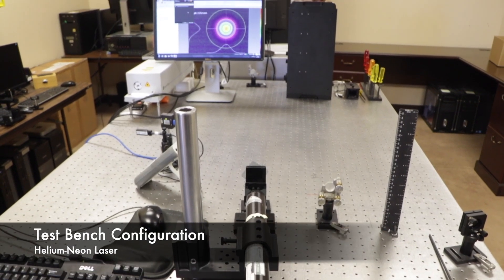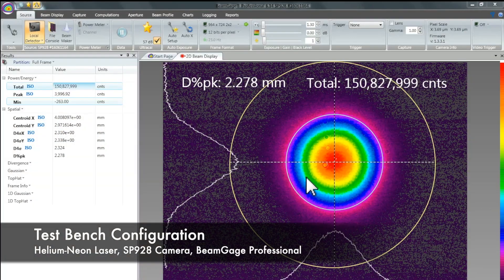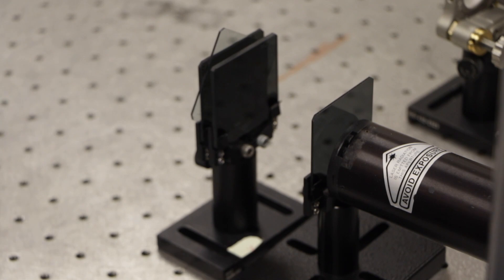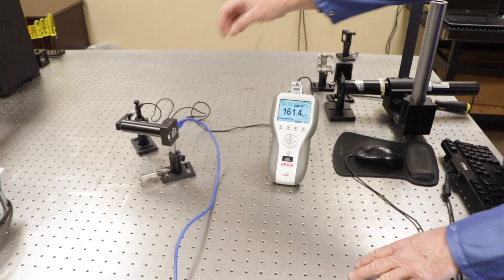We have set up a test bench with a green helium neon laser and an SP928 camera with BeamGage Professional. The beam is attenuated with an assortment of ND filters. We will first measure the beam energy with an Ophir Vega power meter by placing a sensor in the beam path.